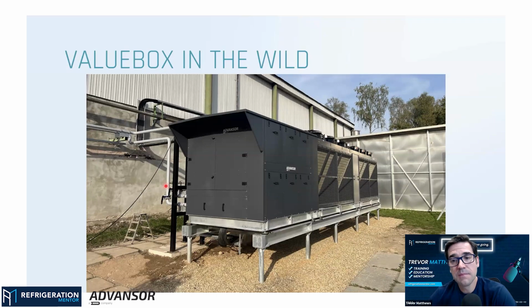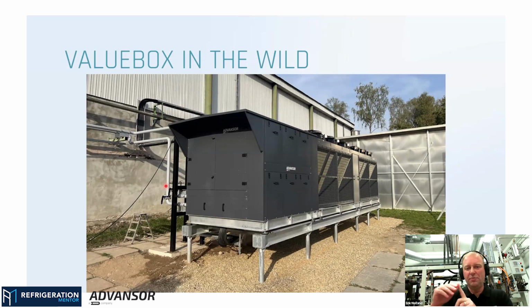Yep. And when you go this fast over a small piece of pipe, you create a suction effect, a small vacuum. This vacuum we are using: the dip tube you usually put into your paint bucket, we put into our suction line from the evaporators. So we are using the high pressure gas to lift the return gas pressure up to receiver pressure level. All this gas is pushed into your liquid receiver without adding any motor work. You don't have a compressor or anything.